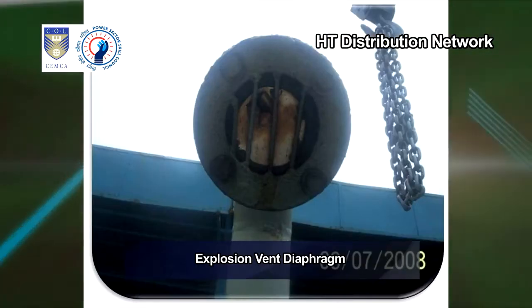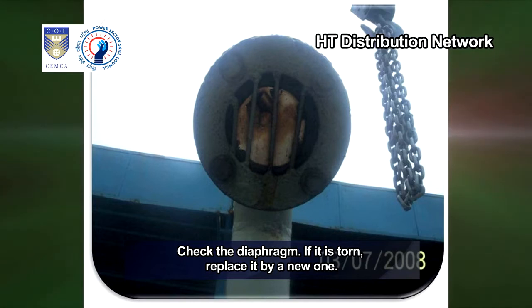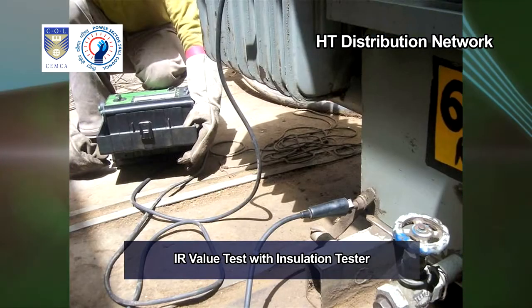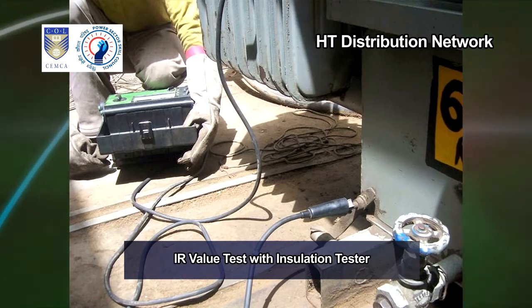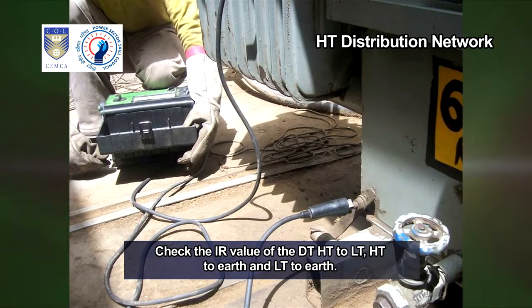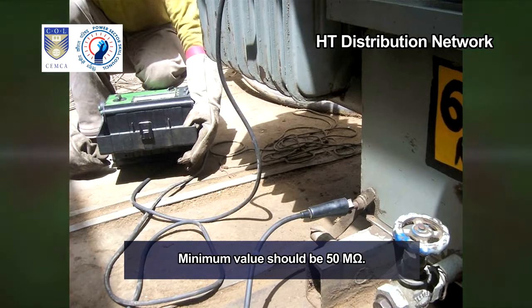Explosion vent diaphragm. Check the diaphragm. If it is torn, replace it by a new one. IR value test with insulation tester. Check the IR value of the DT HT to LT, HT to earth and LT to earth. Minimum value should be 50 megohms.